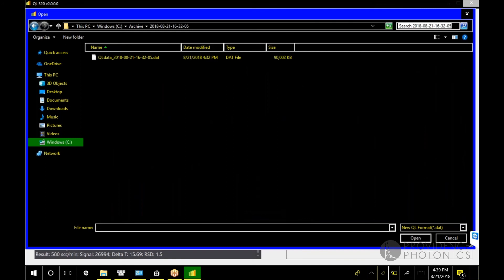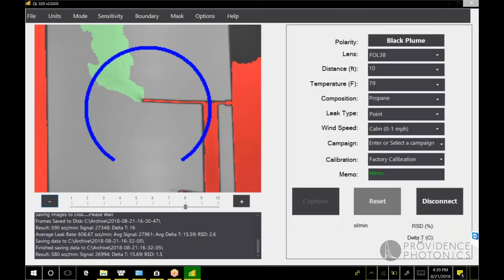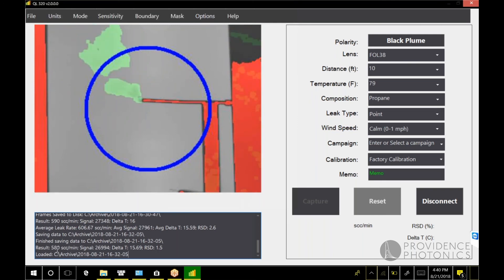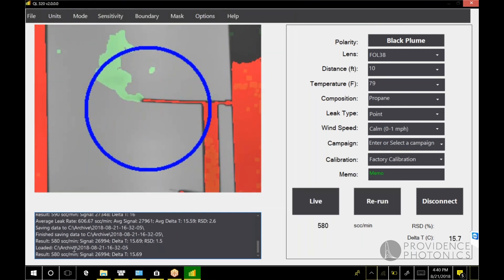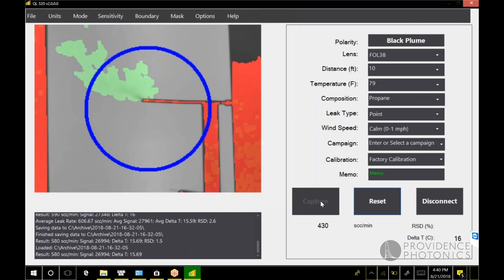Now all of your data, all of your metadata and image data, is written to a single file which is date time stamped and has an extension of dot dat. So if I select this file and load it, it's now playing back that recorded image that we recorded a few minutes ago. Everything you need is in that single file, so it's a lot easier to manage the archive data. You see I got the same result as when we recorded it. After you look at an archive file, you can always hit the live button and go back and now we're looking at a streaming image again.